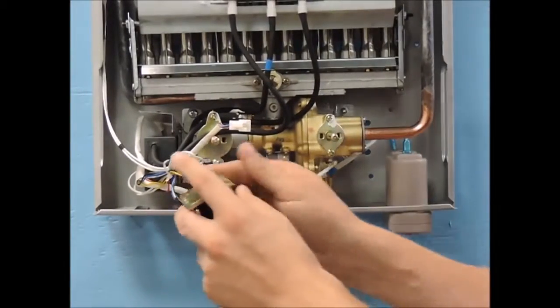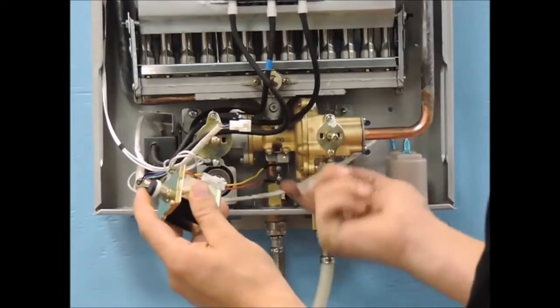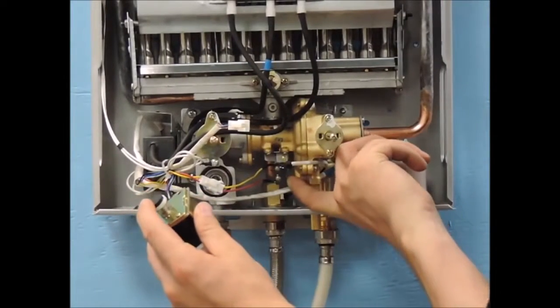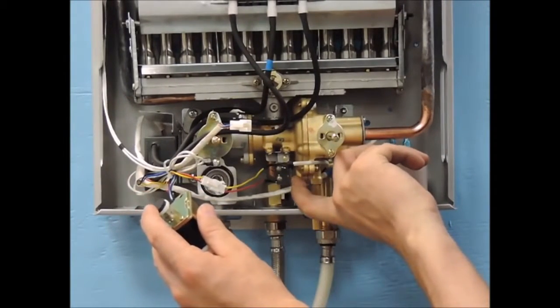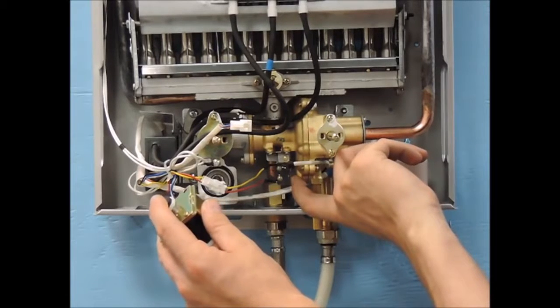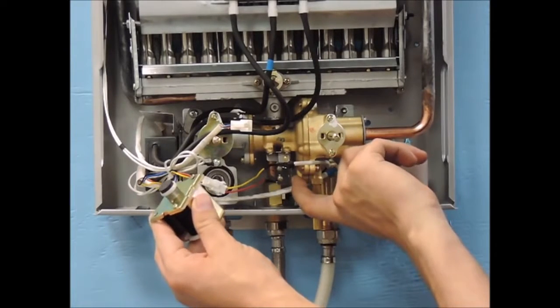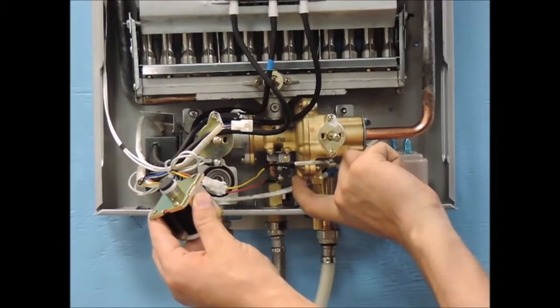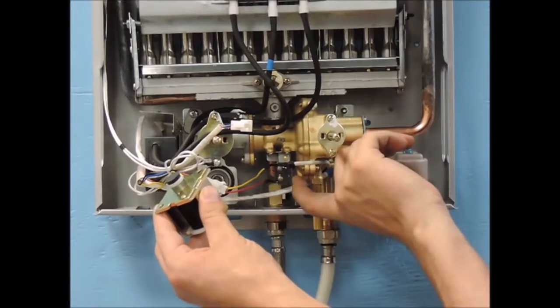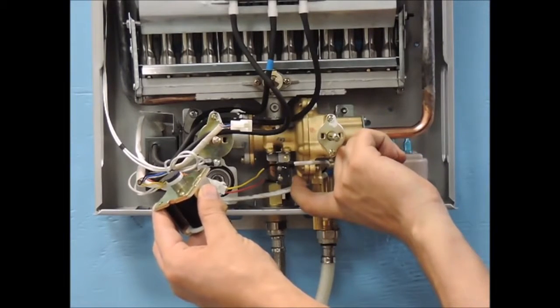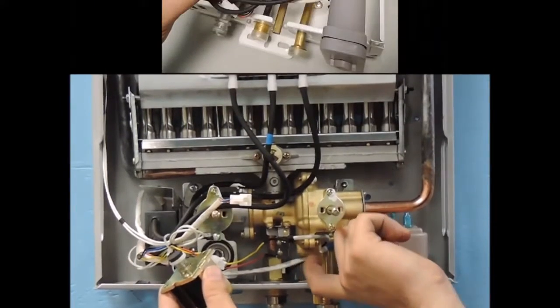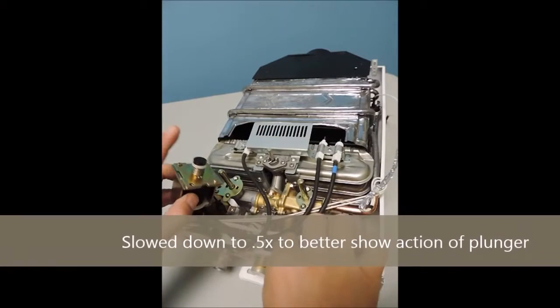As you lift the micro switch, you will want to listen for the sound of the solenoid opening. It's a distinctive, loud clacking noise. As you keep the micro switch open for roughly 20 seconds, you will hear the solenoid close. There will be a softer thump noise. You can amplify these sounds by holding the tip of a screwdriver on the solenoid and lightly resting your ear on the base of the screwdriver handle.